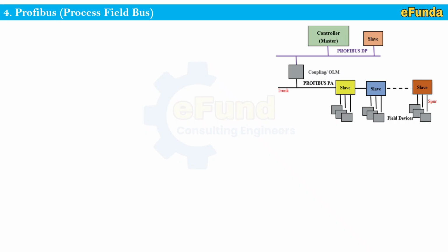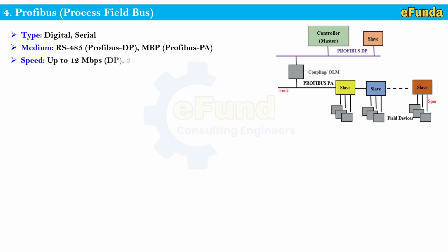The interface is handled with the help of Profibus, and we'll see the details: type digital serial, medium RS485, Profibus DP and MBP, that is Profibus PA. Speed up to 12 Mbps for DP and 31.25 kilobits per second for PA. Topology is bus type, and variants one can see as well.